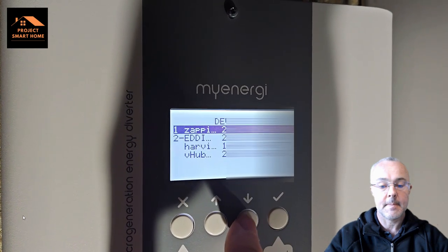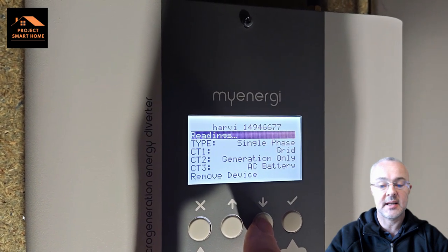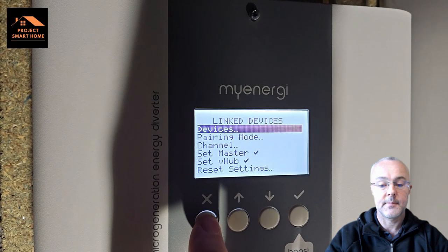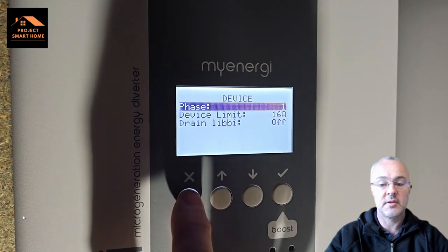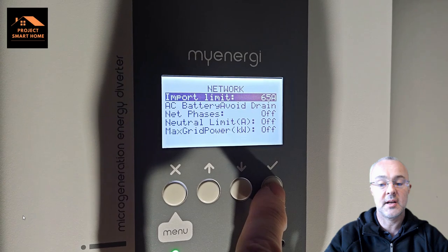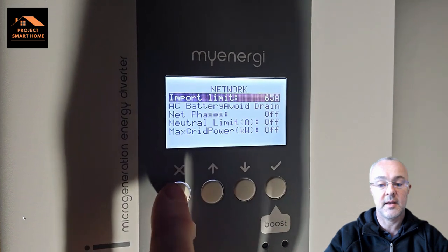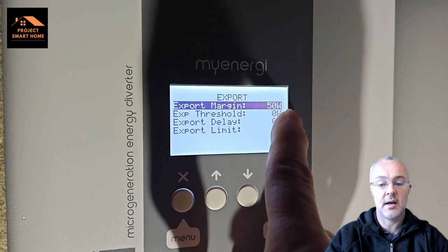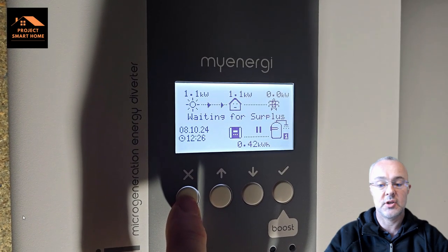In the harvi — where the CT clamps are connected — I've got grid connected, solar connected, and AC battery connected. From a grid point of view it's single phase with a 65 amp network limit, so I'll never consume more than that. My export margin is set to 50 watts, so any time I'm detecting more than 50 watts going back onto the grid I start redirecting it back into my energy infrastructure.